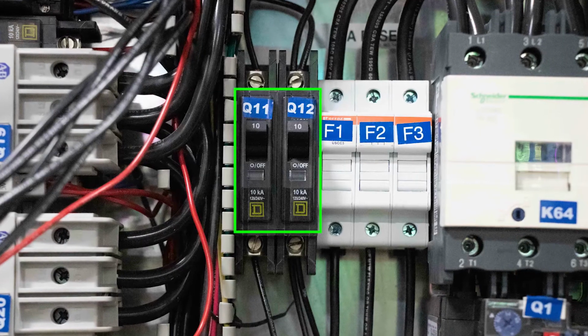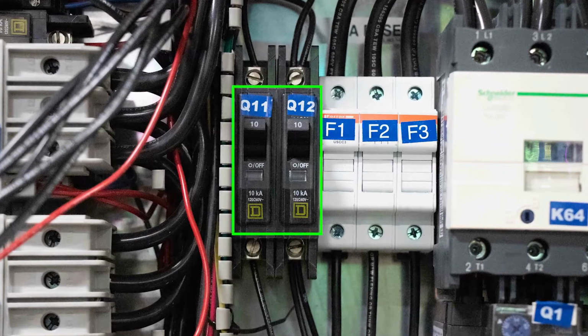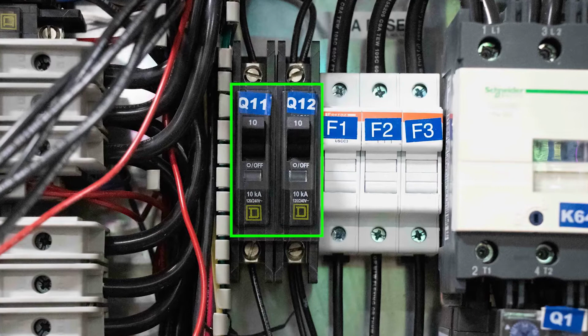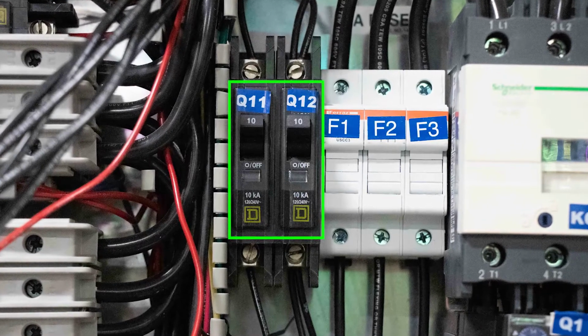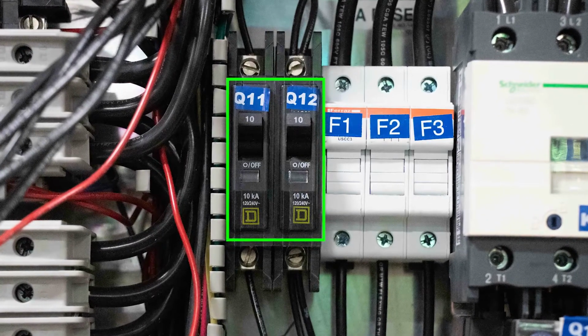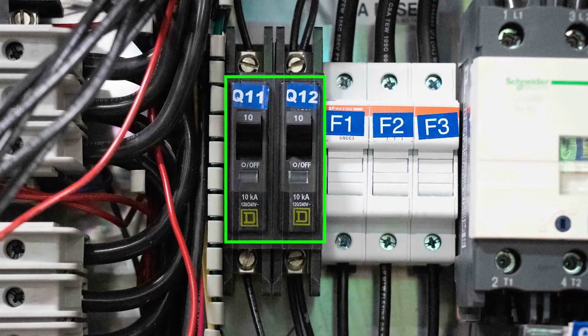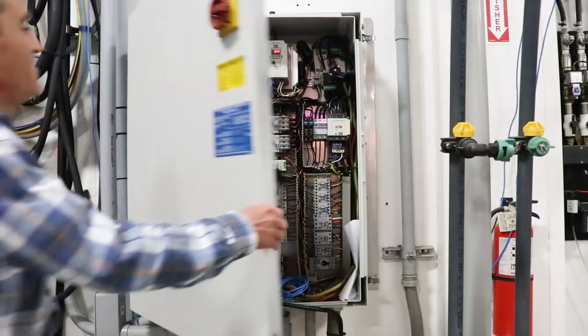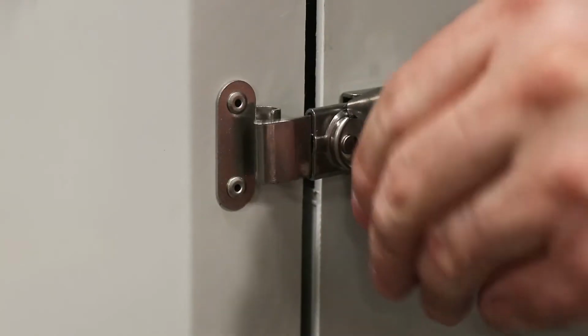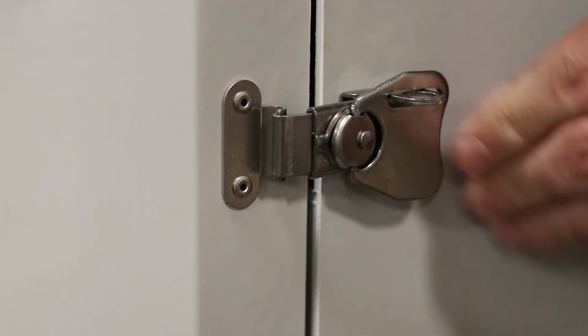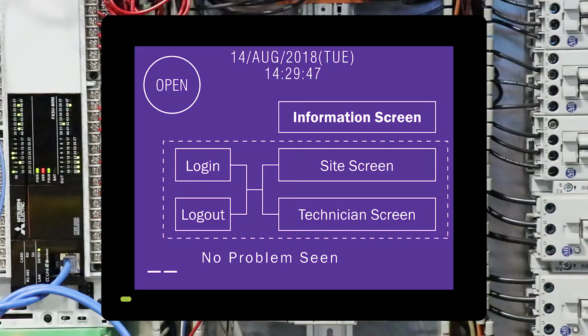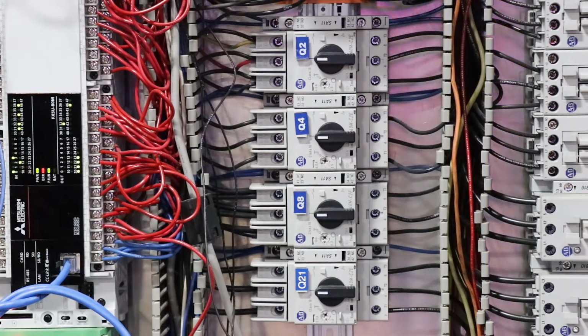You may also notice this style that looks like a regular circuit breaker that you might find in your own home. If one of these is tripped, the lever will be in the middle. You will have to turn it off and then back on. Close the cover and relatch the top and bottom latches to make sure it's watertight. Then turn on the power switch and see if the error code is cleared on the HMI. If the overload continues to trip, call for service.